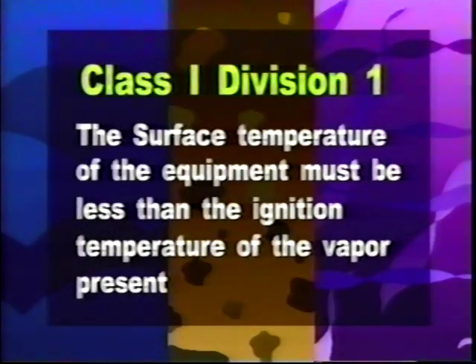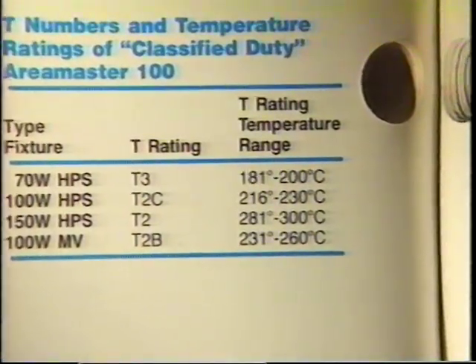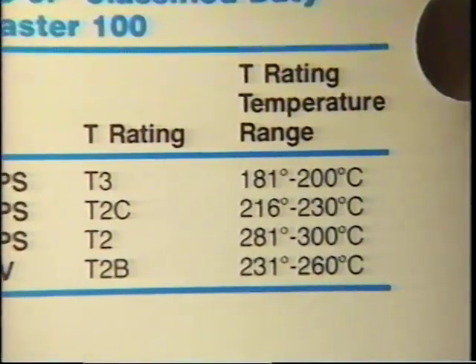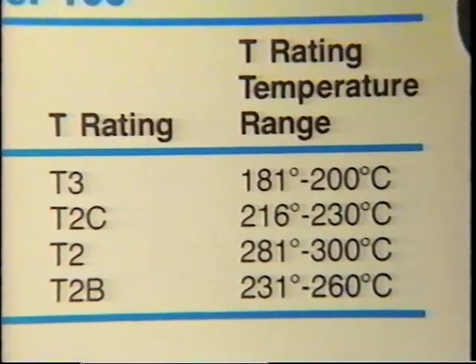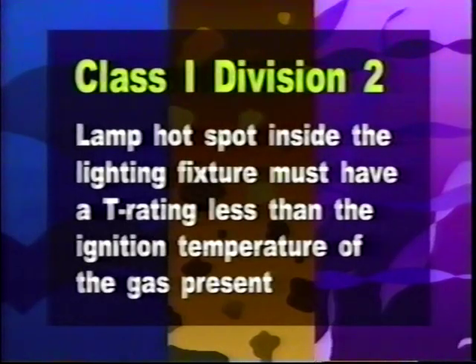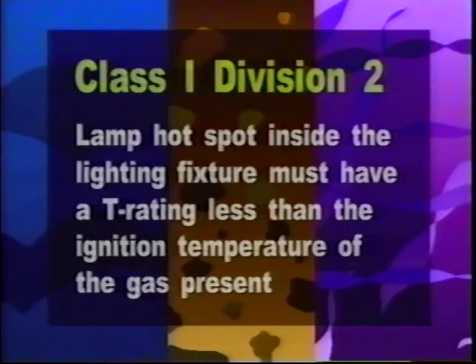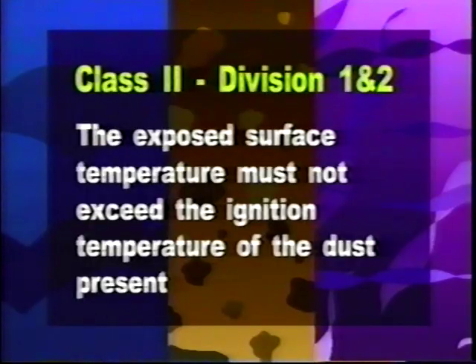In a Class 1, Division 1 area, the surface temperature of the equipment must be less than the ignition temperature of the vapor present. Equipment that is heat-producing, such as fixtures and motors, are all tested and assigned T numbers. The T number is a rating that indicates the maximum external surface temperature of the equipment, and it relates to a temperature range chart in the NEC. Higher T numbers indicate cooler running equipment, and the T number must appear on equipment nameplates. For Division 2 areas, the lamp hotspot inside the lighting fixture must have a T rating less than the ignition temperature of the gas present. For Class 2 Divisions 1 and 2 areas, the exposed surface temperature must not exceed the ignition temperature of the dust present. Zone T ratings are the same as Class Division T ratings, except they don't have the letter suffixes.